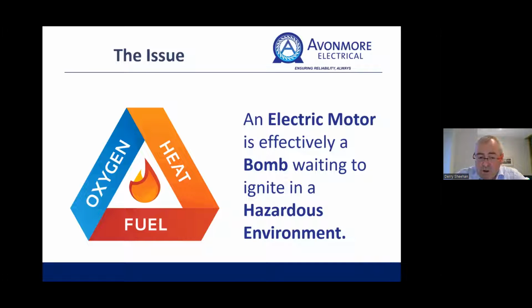The terminal block is the obvious one. The bearings, if they fail, can be many hundreds of degrees. On an EX motor, they're typically rated T4, the most common rating, which is 135 degrees. Now that's not really hot when you come to something like a bearing temperature.